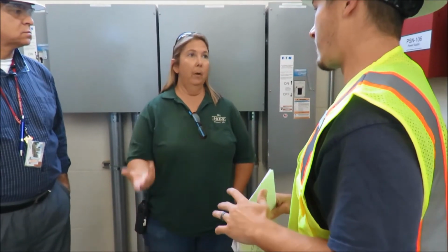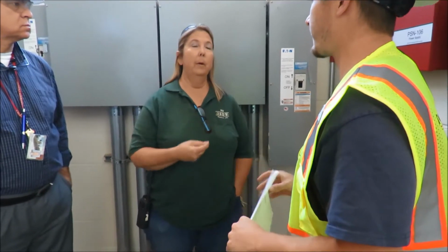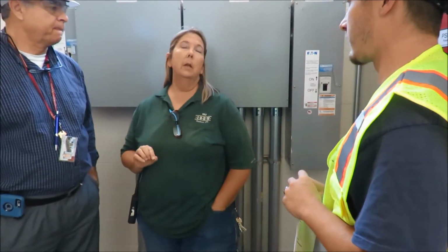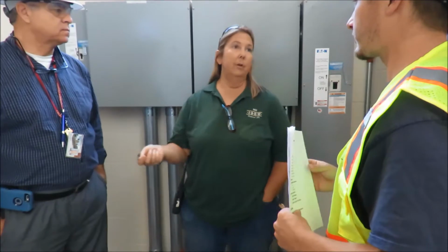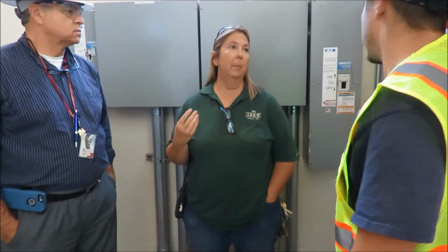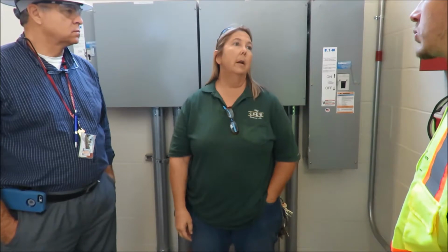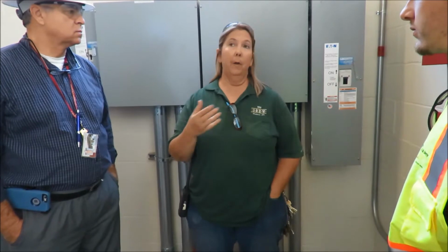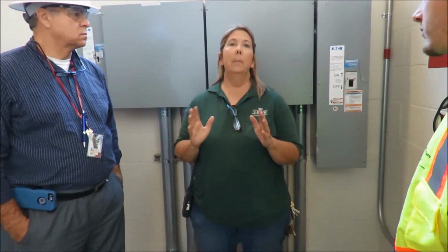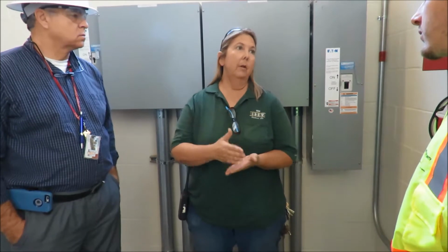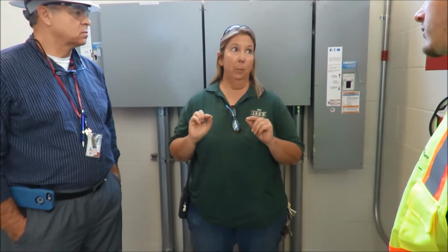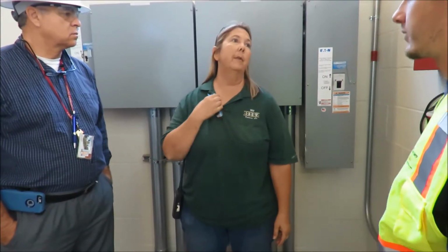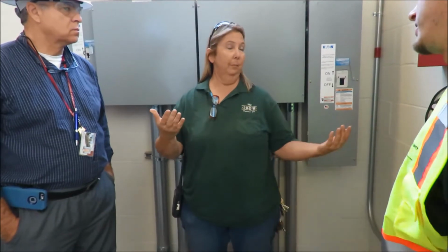And then at some point, and I know this job's done, sorry, a little bit off topic, student housing 3. Between the engineers and myself, we would like to somehow monitor the PAM relay. I'm not sure how we can do that, either through the HVAC, which is possible, or through the fire alarm. We don't really care. But what happens is that we have a failure, we have dampers closed, and when we realize what's happened, it's somebody complaining, oh my God, it's so hot in here. So we don't want that anymore. Trying to get a heads up on the issue.